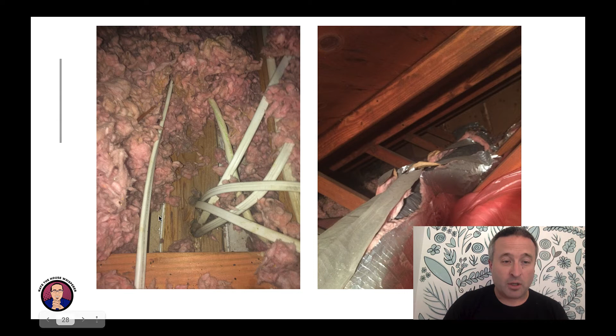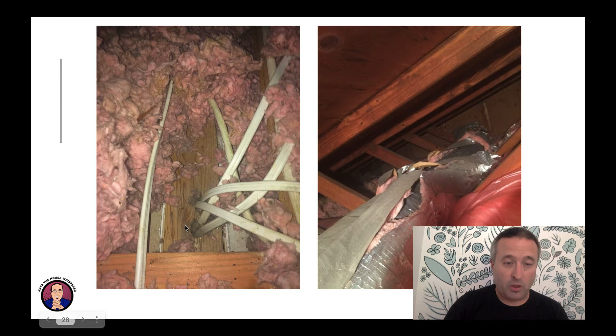Top plates are another super common thing. Here's the ceiling of one room, here's the ceiling of another room, and this is the wall in between them. Note the dirty fiberglass here. Whenever you see dirty fiberglass, that almost always means air leakage, it's filtering the dirt out of the air flowing through it. That's almost always what's happening, and top plates are a very common leakage point.